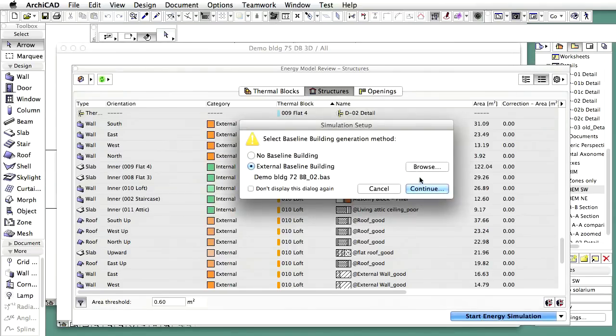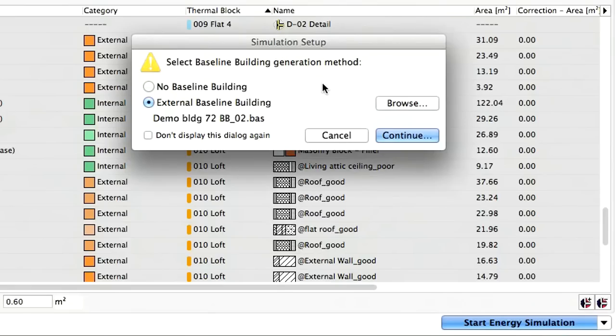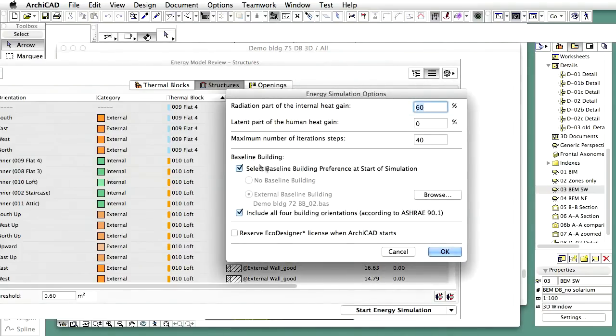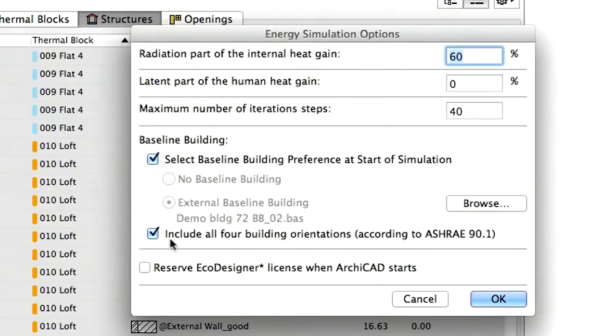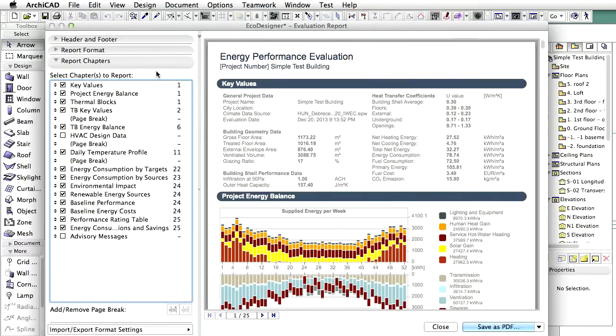In order to enable the performance rating, the previously created external baseline building reference file must be used. There are two different ways EcoDesigner STAR can use the baseline building reference file: a straight-up performance comparison with the designed building's performance, or the baseline building reference data is first automatically processed by the program according to the ASHRAE 90.1 standard, and the resultant data is then used for energy performance comparison. Once the analysis is completed, the Energy Performance Evaluation Report dialog appears.